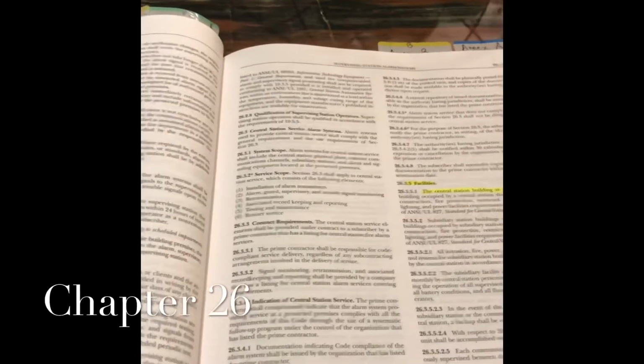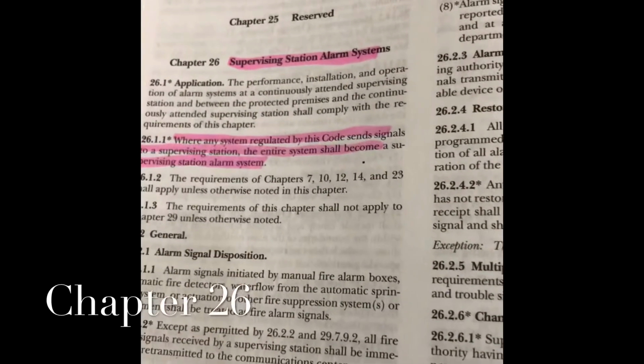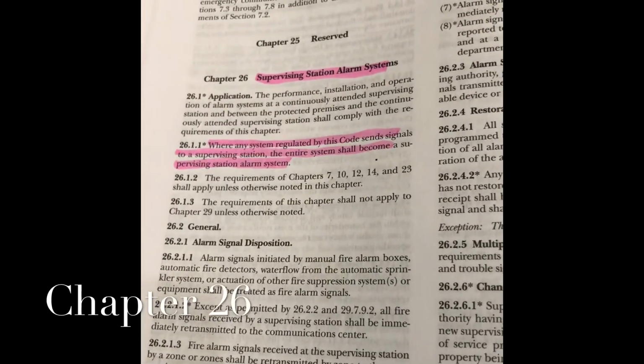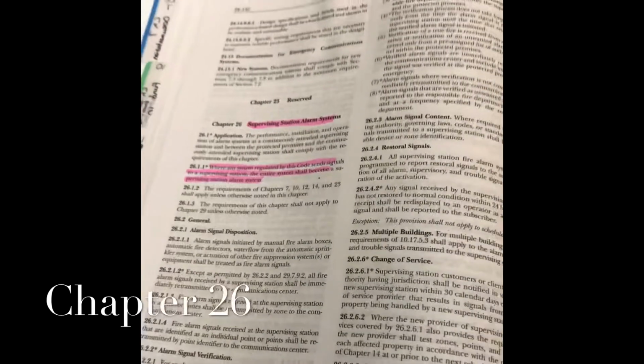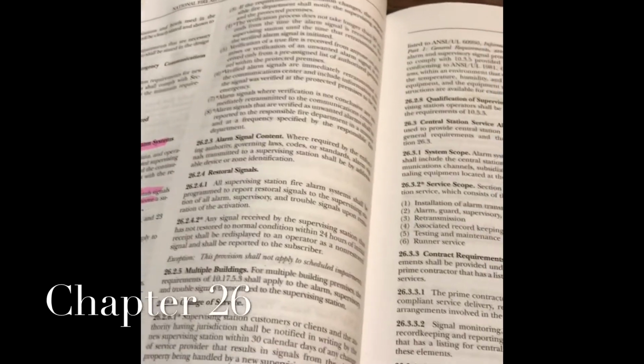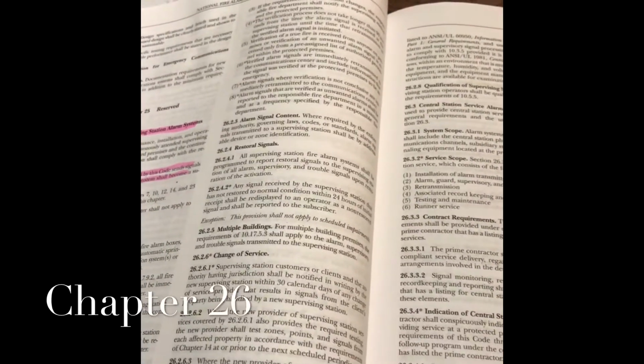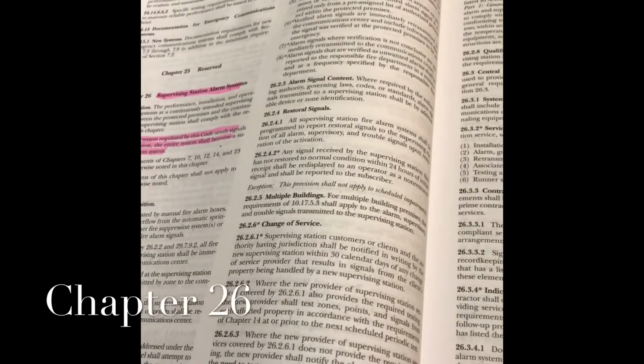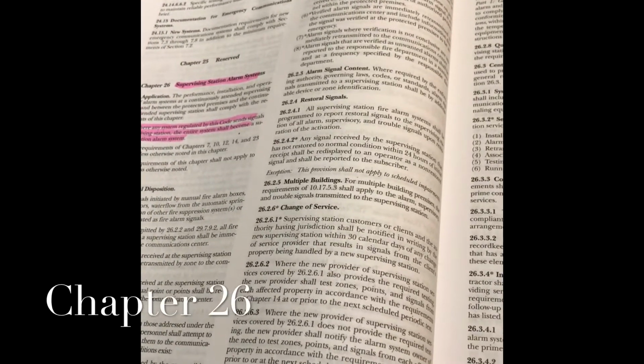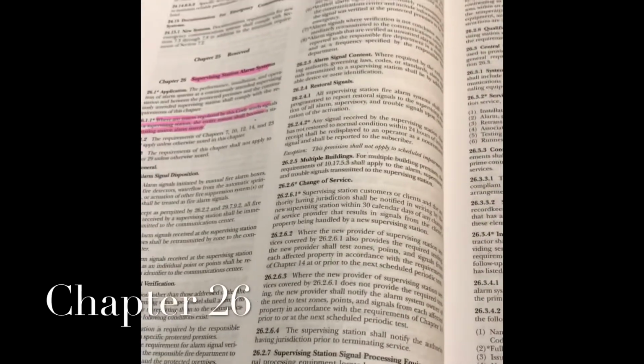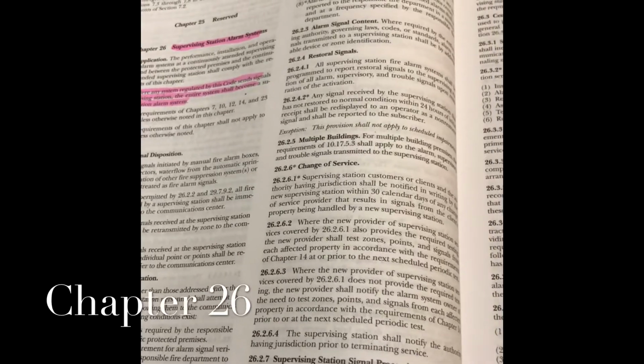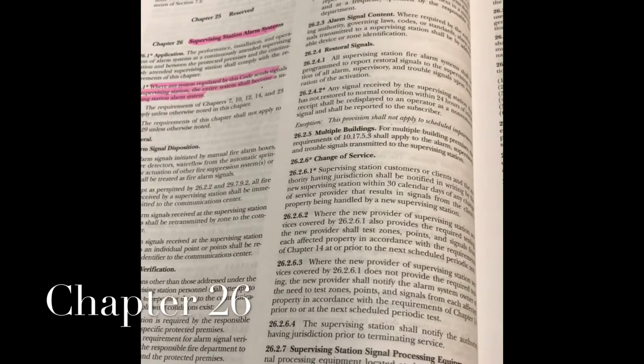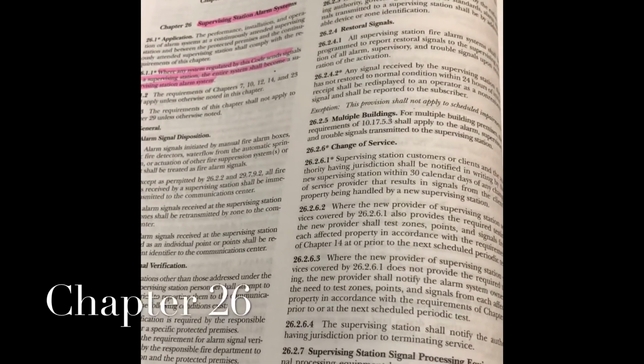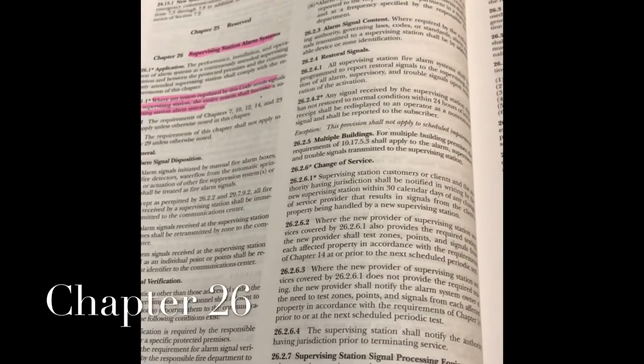Alright, so today I just want to go over chapter 26, Supervisory Station Alarm Systems. What chapter 26 deals with is basically how the communications takes place from the fire panel to a station that is pretty much supervising the fire alarm system. Now you also have to remember that there are 3 types of systems that supervise. You can have a central station, you can have a proprietary, or you can have a remote station. Those are the main 3.